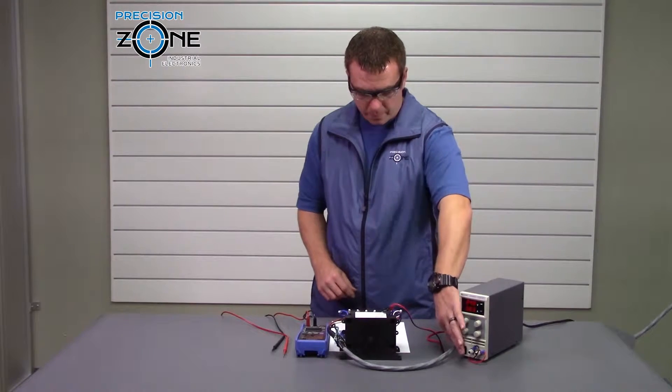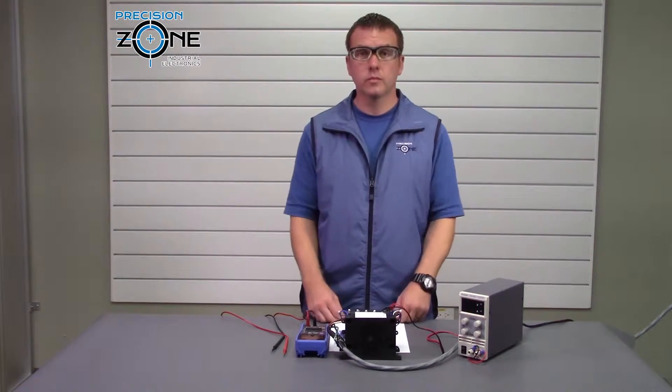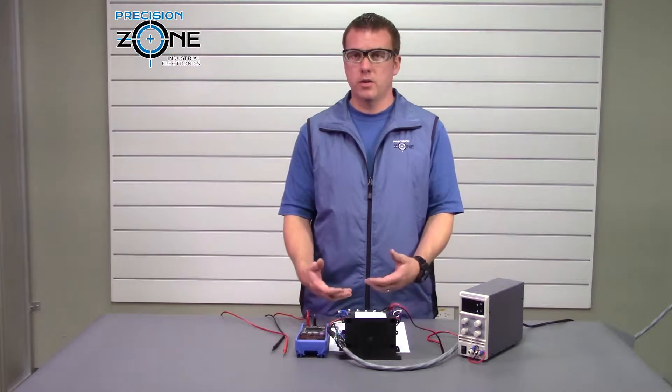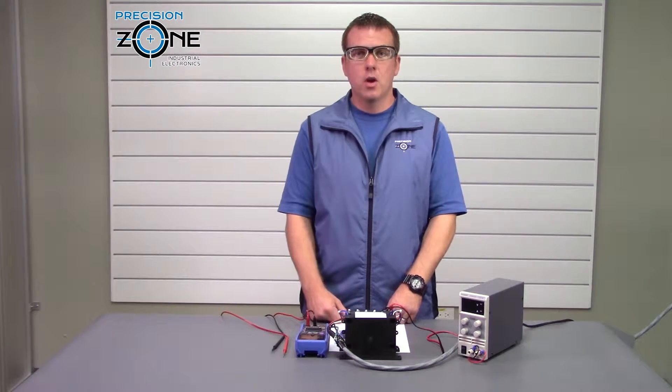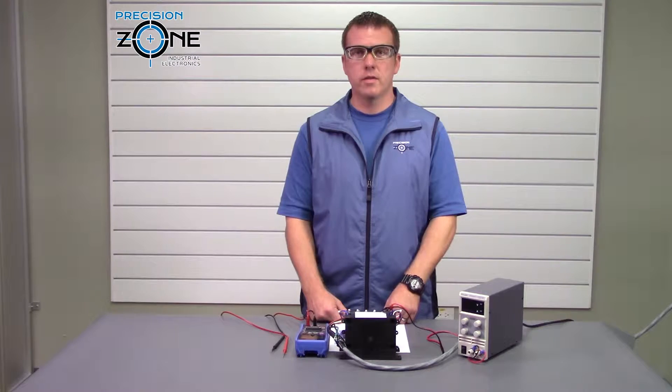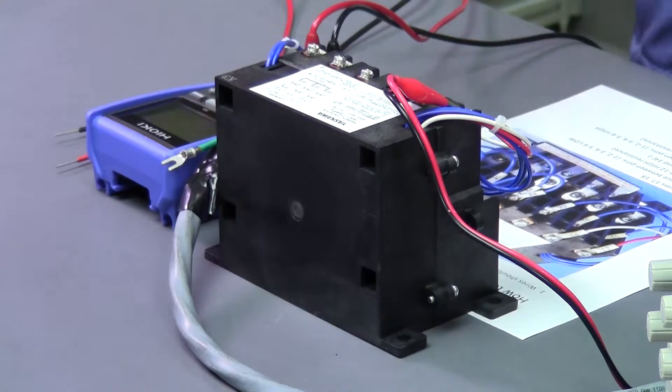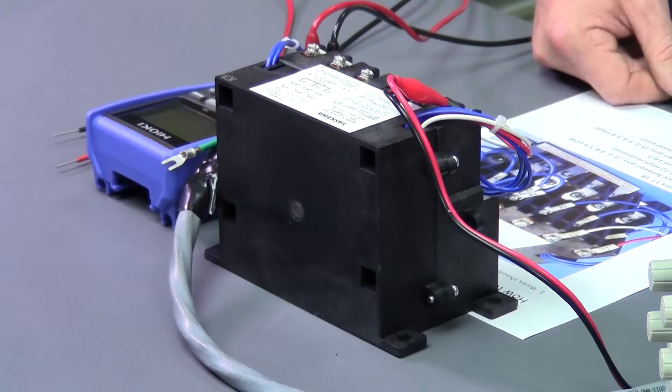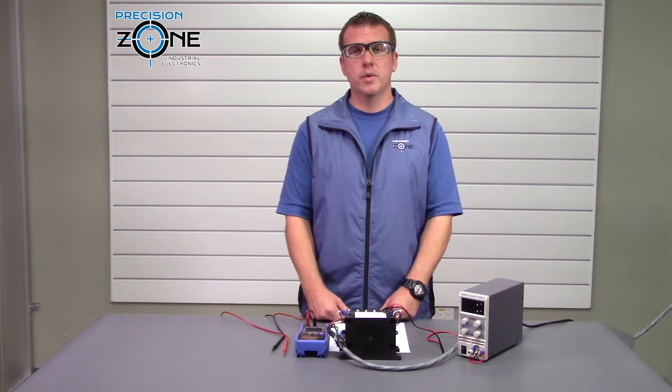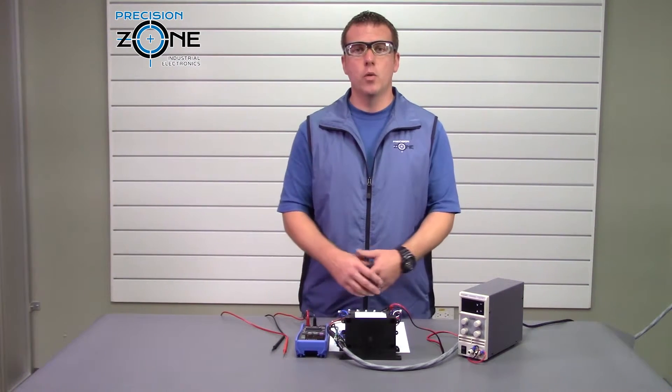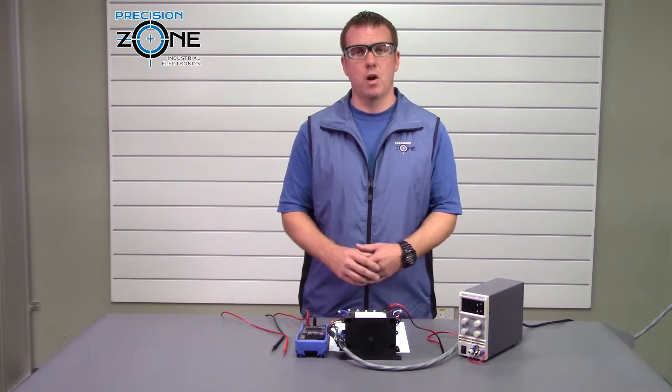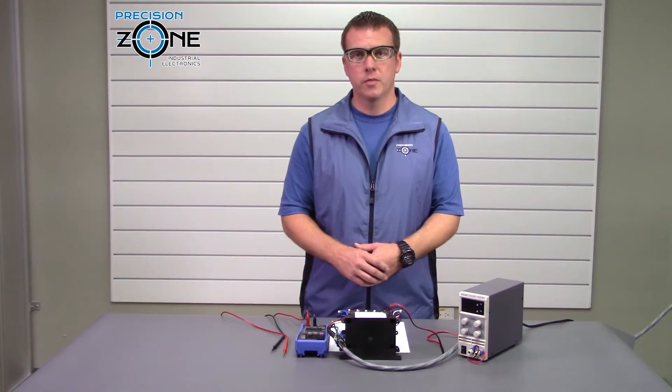So this contactor checks perfectly fine and there's nothing wrong with it. But if you do have a spindle drive that comes in for repair, we always recommend that you change this contactor because it's just cheap insurance to make sure the drive didn't damage it. So please go check us out at PrecisionZone.com if you have any more questions. We perform free motor evaluations and we provide warranties on all the products we repair. Thanks for watching.